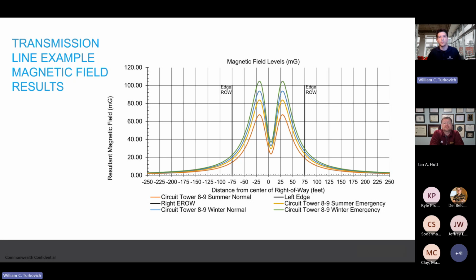One thing I would also note is you can see the bars that show the edge of the right of way, but we've also plotted and calculated far beyond that, up to 500 feet total in this example. And maybe you're a utility that's building a line and there's a person who has a house 125 feet from the center line of your line, and they're concerned about the electric or magnetic fields affecting them. When we run the study, we have that extra data to show them exactly how much those levels are relative to safety limits, and maybe be able to add some comfort to that answer for that concerned person.